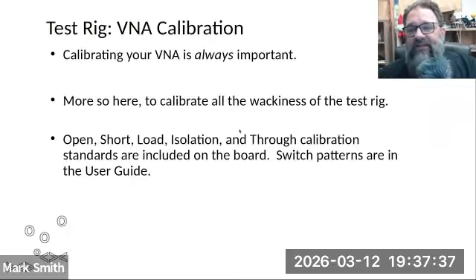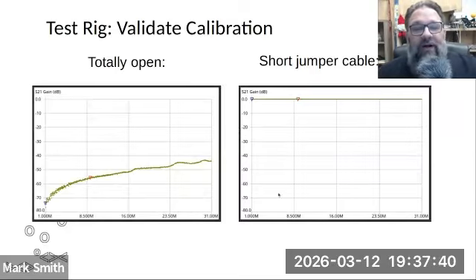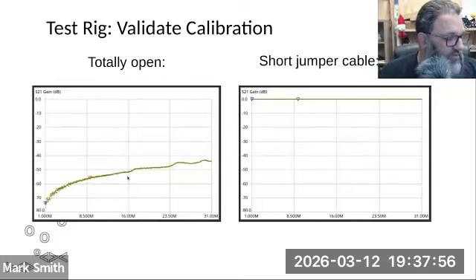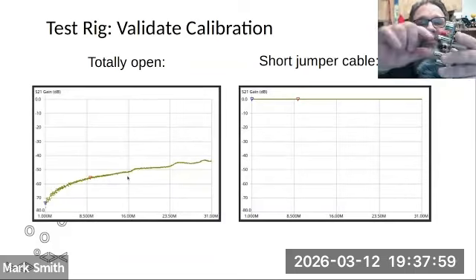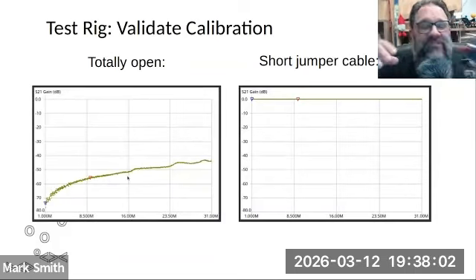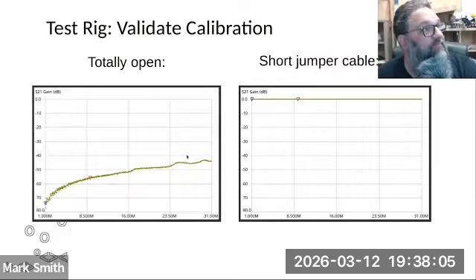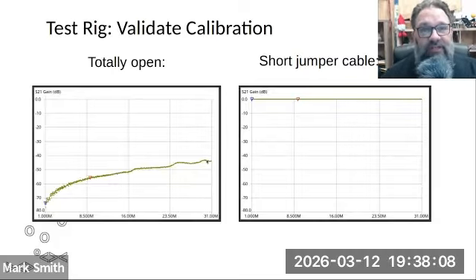All right, so let's start taking some... Oh, no, sorry. First off, the next thing you do after you calibrate it is validate your calibration. So when you have a totally open, this is the isolation mode of your calibration, you should be reading nothing. It should be down here at -80 or less. The common mode current choke test rig is kind of big, and there are capacitances between these parts, so it's not perfect. But we get up to about minus 45 dB of crosstalk between the two channels when the test rig is connected. That's okay because we are interested in reading around 20, 25, maybe 30 dB.